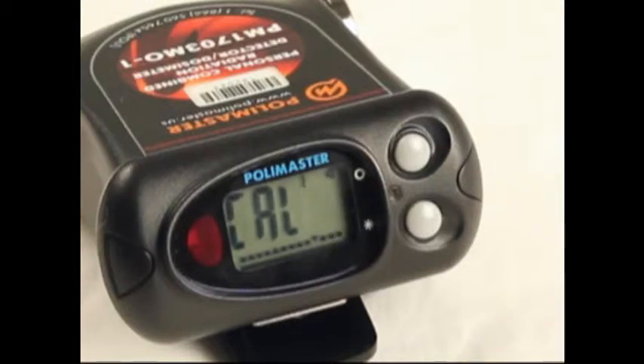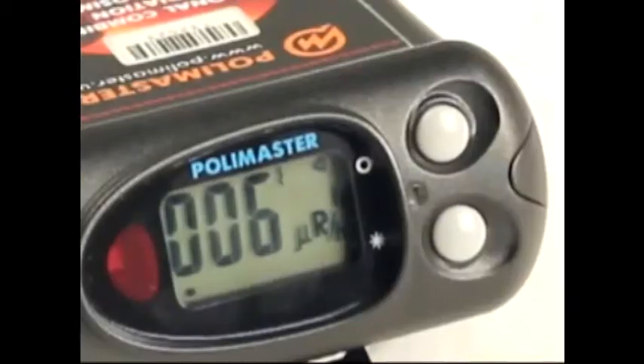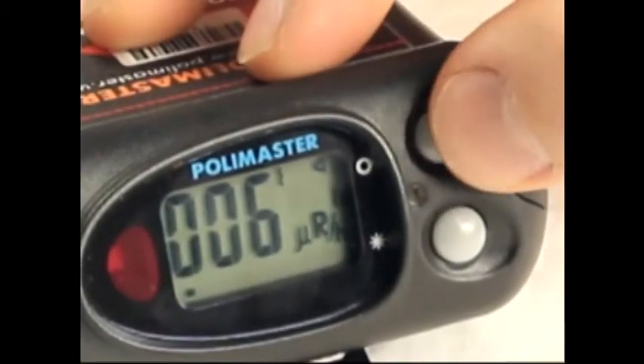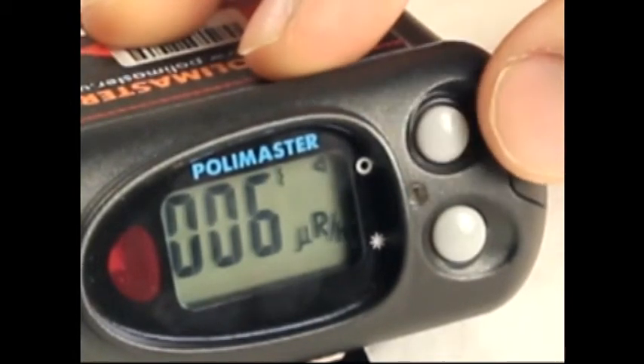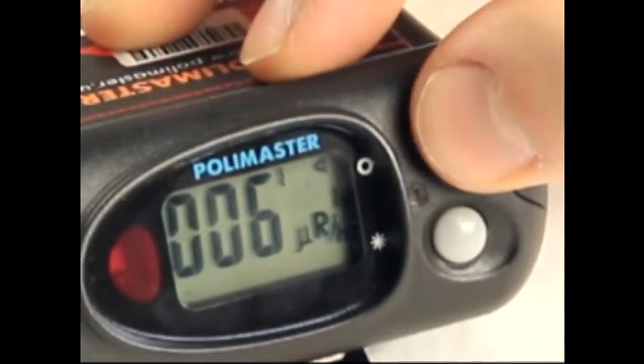Upon the completion of Calibration Mode, the detector goes into Dose Mode. To change between Dose Mode, Search Mode, and Accumulated Dose, press the Mode button. Search Mode is indicated by a flashing S on the display.